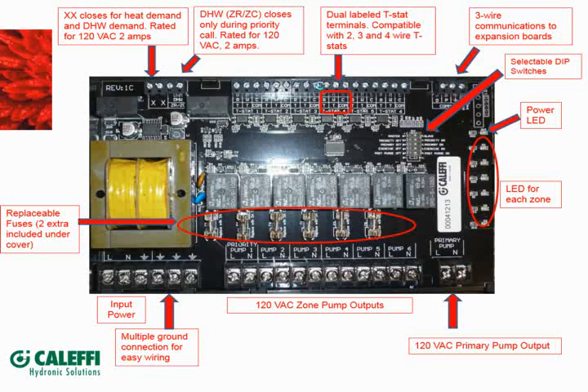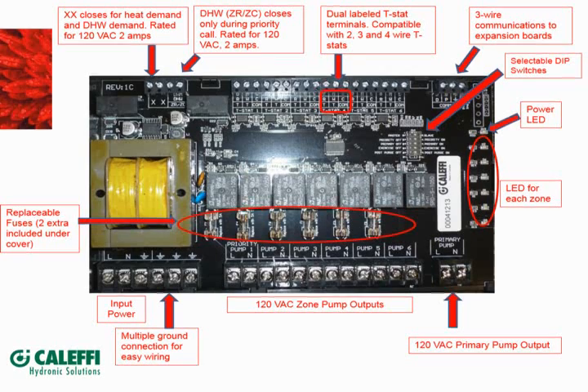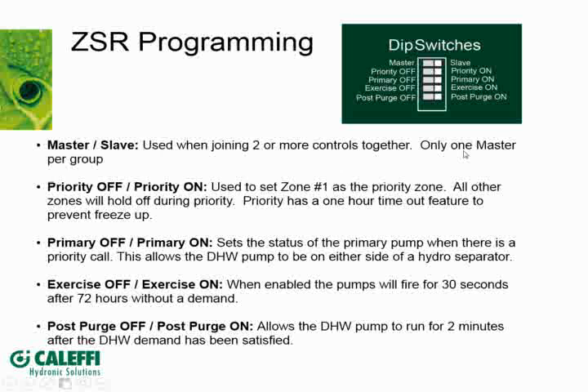So this is how the programming takes place. I mentioned that we have dip switches. The master-slave switch, of course, is used if you have 2 or more controls together. You can only have 1 master per group of boards. The priority on or off is used to set zone number 1 as the priority zone. That's typically done for a domestic hot water heater, an indirect. If that zone calls, all the other zones are going to hold off during that priority call.